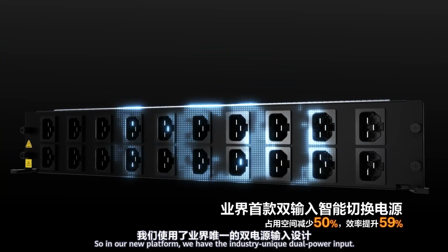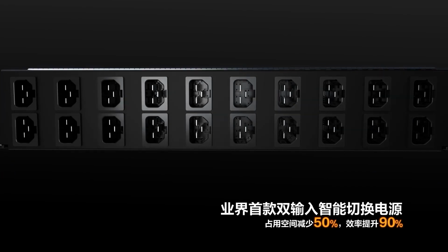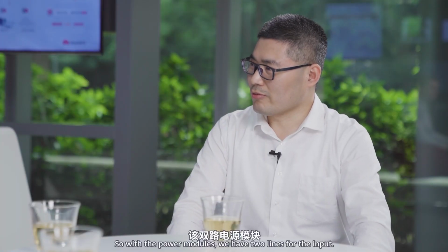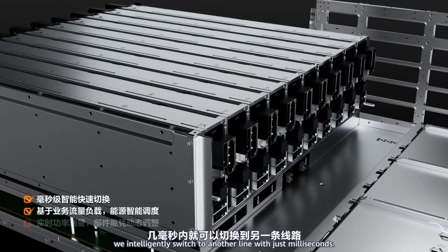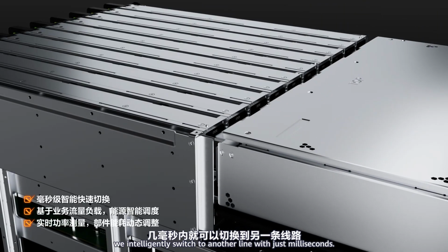Yes, it's a good question. So in our new platform, we have the industry-unique dual power input. With the power modules, we have two lines for the input. We have the intelligent switching functions. So if one line has a fault, we intelligently switch to another line within just milliseconds. You wouldn't notice anything, it has already changed to another line.